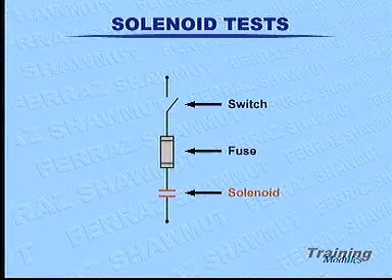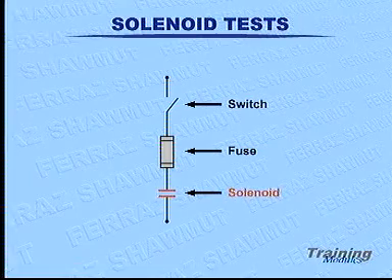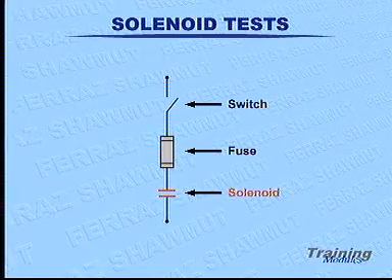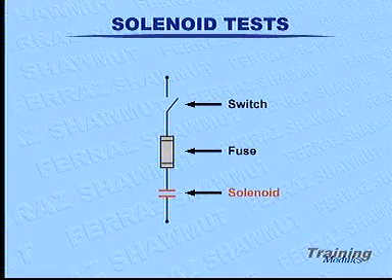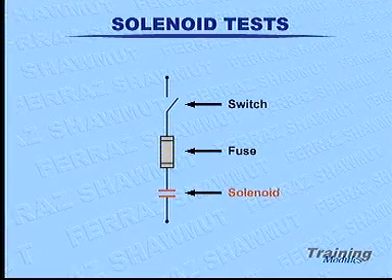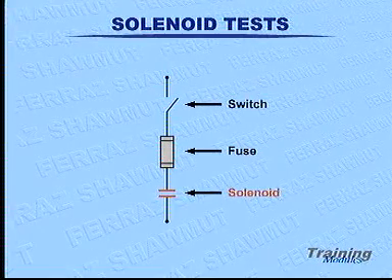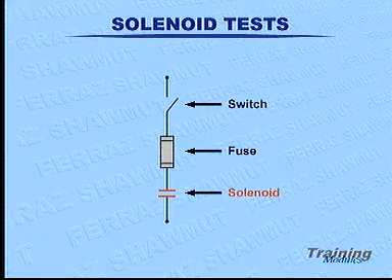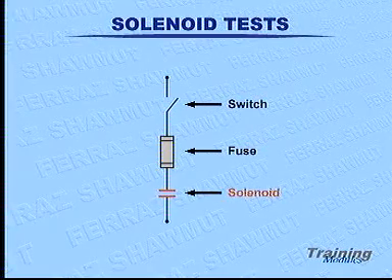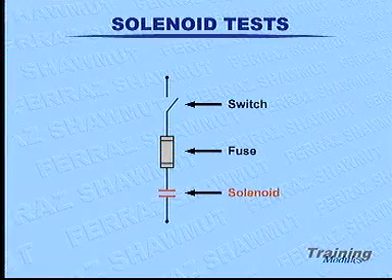The purpose of these tests is to explain the differences between fast-acting and time delay fuses, as well as to clarify any possible misconceptions about time delay fuses. For inrush applications like motors, transformers, and solenoids, the thermal capacity of a fuse in the overload region determines how it should be applied. The goal is not only to avoid needless openings on temporary harmless overloads, but also to ensure proper protection against longer, dangerous overloads.